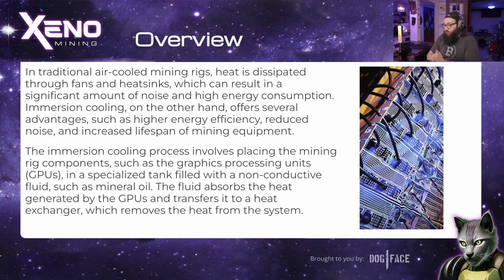So the immersion cooling process involves placing the mining rig components, such as graphic processing units or ASICs, in a specialized tank filled with a non-conductive fluid like mineral oil. This is just one example, and I'll go over the difference between things like dedicated dielectric fluid versus mineral oil. But the idea is the fluid absorbs the heat generated by the GPUs or ASICs, and transfers it to an exchanger, which removes the heat from the system - just like a pipe system that happens for this to work.